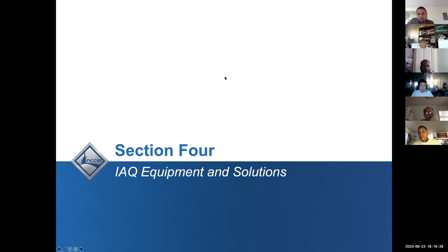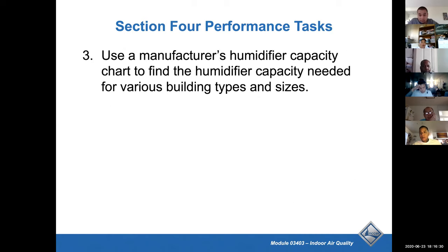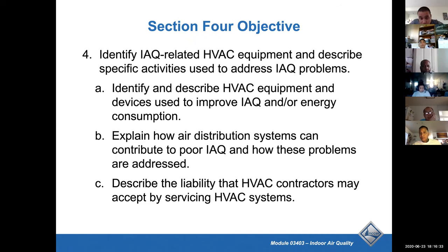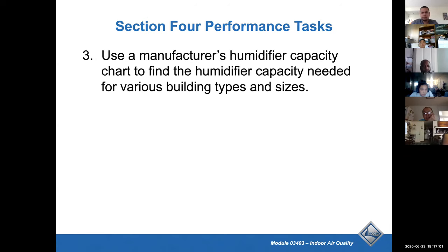Indoor air quality equipment. Okay, you should be able to identify IAQ equipment, and identify and describe HVAC equipment and devices used to improve IAQ. Explain how air distribution systems can contribute to poor IAQ and how these can be addressed. Liability HVAC contractors may accept by servicing HVAC systems. Use the manufacturer's humidifier capacity chart to find humidifier capacity needed for various building types and sizes.